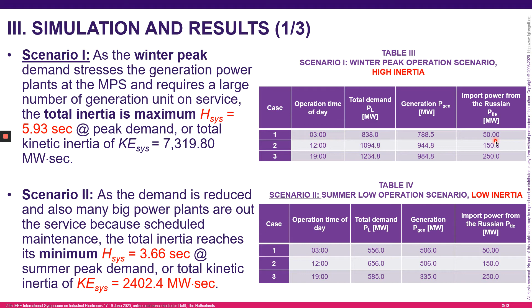Okay. Simulation results for case number 1, for scenario number 1, the high inertia system. As you can see over here, if we think about the maximum, case number 3, where we have the maximum power transfer of 250 megawatts from Russia to Mongolia, we can see over here that the minimum frequency is reaching 48.3 hertz, and after the under frequency load shedding intervenes, all 3 stages of the under frequency relay trip, and as a consequence, the final steady state frequency is 48.83.